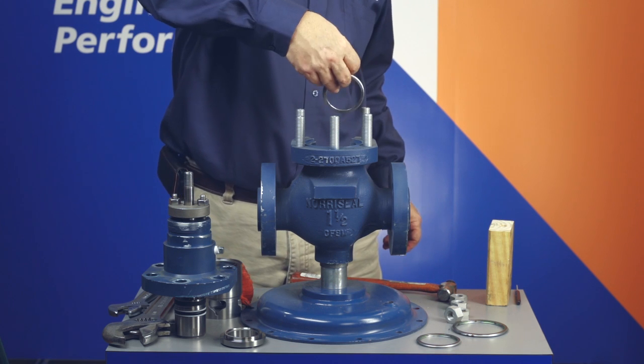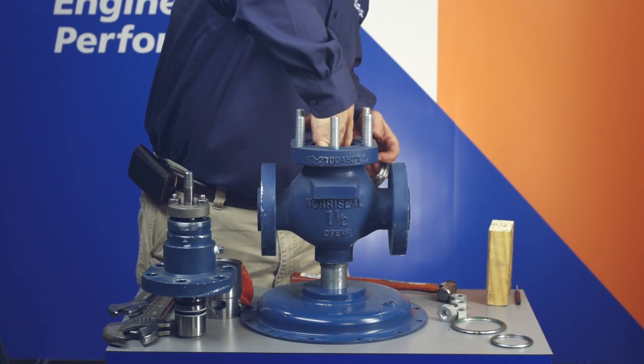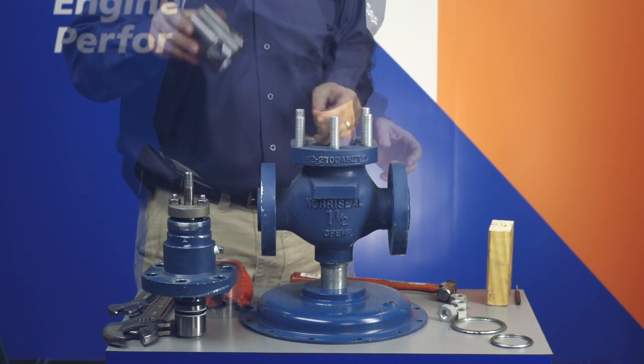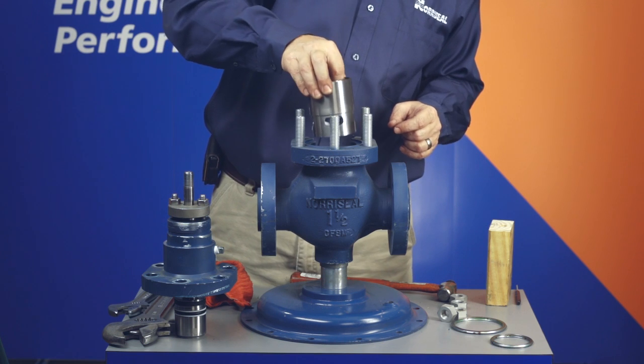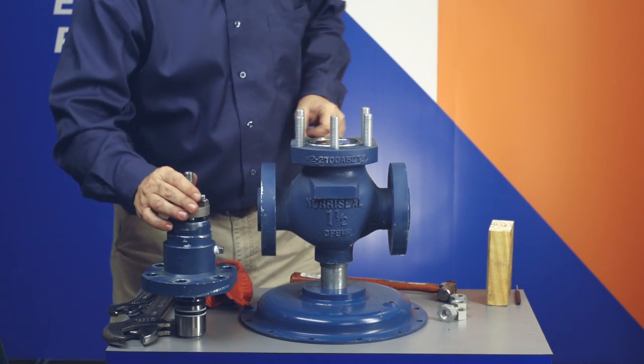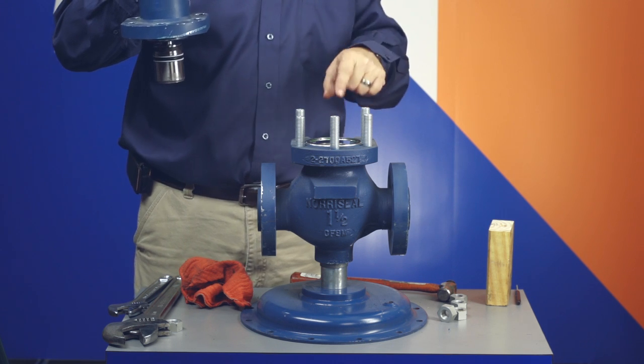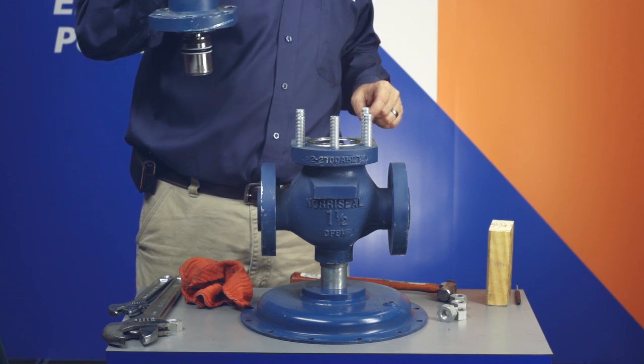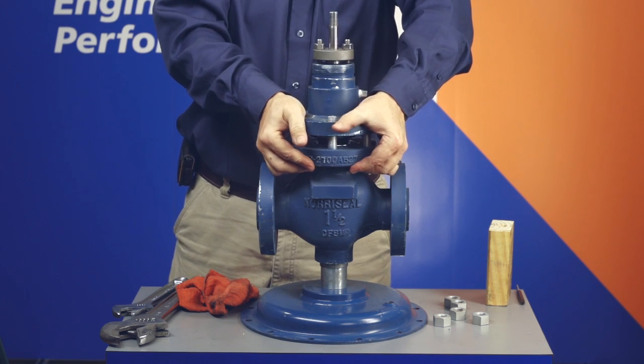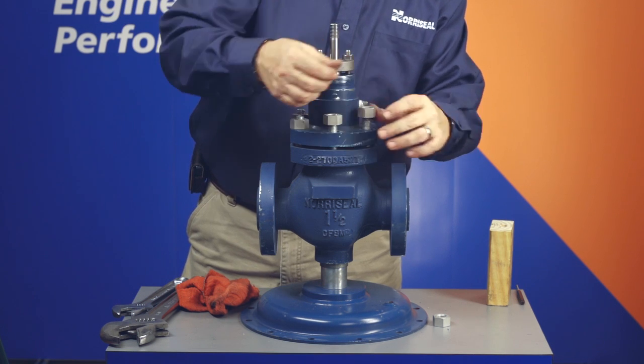Install the new seat gasket into the cavity in the body's bridge wall, and then install the seat ring into the body's cavity. If the valve has a soft seat, install the seat insert in the groove on top of the ring. Install the cage on top of the ring, and then install the new bonnet gasket into the top valve body flange recess. Install the new cage gasket in the groove on top of the cage, and lower the bonnet stem plug assembly onto the body, guiding the plug into the cage.